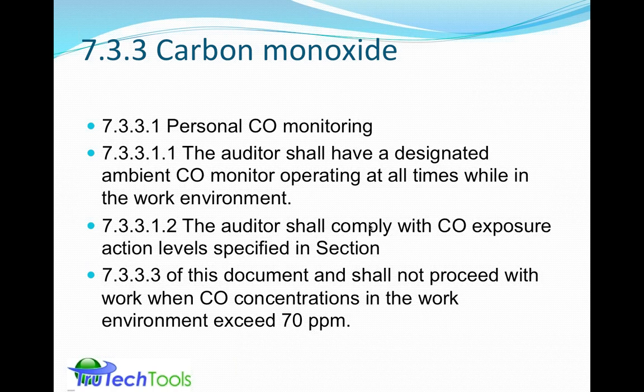For the carbon monoxide factor, you should have the carbon monoxide monitor operating at all times when you're in that work environment as described previously, and comply with the CO level exposure action levels, which are next. And then the bottom line is here: do not proceed with CO work when the CO concentrations in the work environment exceed 70 parts per million ambient level.